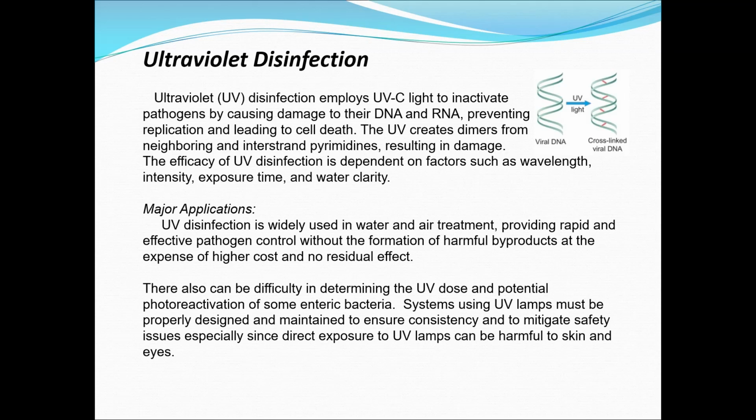Ultraviolet, or UV, disinfection employs UVC light, a higher frequency UV light, to inactivate pathogens by causing damage to their DNA and RNA, preventing replication and leading to cell death. UV disinfection is widely used in water and air treatment, providing rapid and effective microbial control without the formation of harmful byproducts. The efficacy of UV disinfection is dependent on factors such as wavelength, intensity, exposure time, and water clarity. UV systems must be carefully designed and maintained to ensure consistent performance, and are often used in conjunction with other disinfection methods to achieve comprehensive microbial reduction.